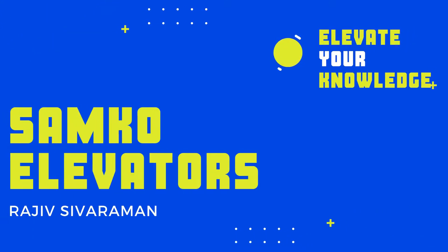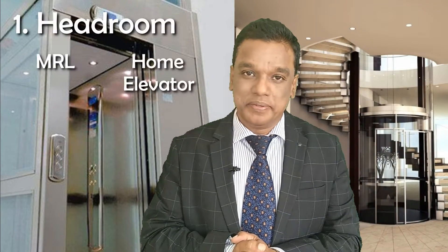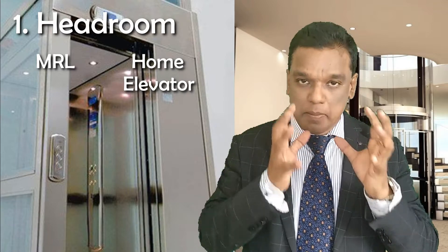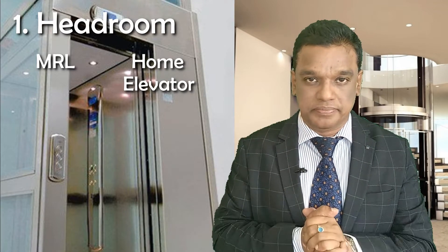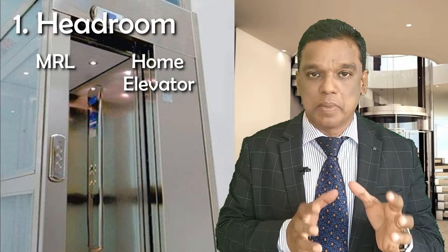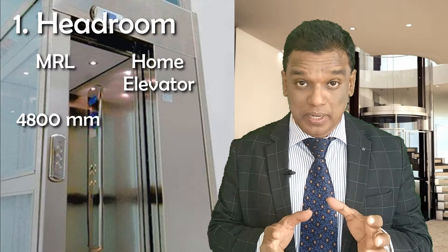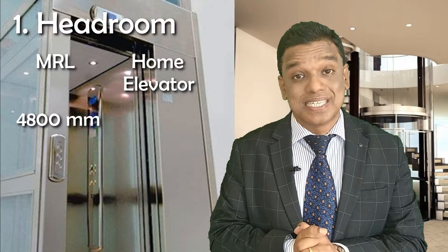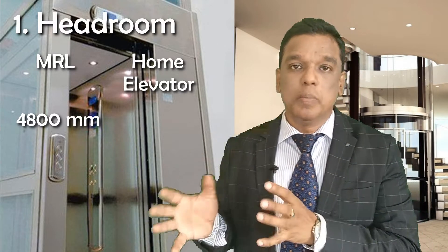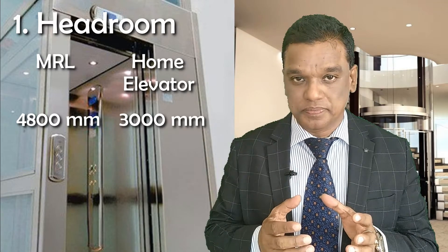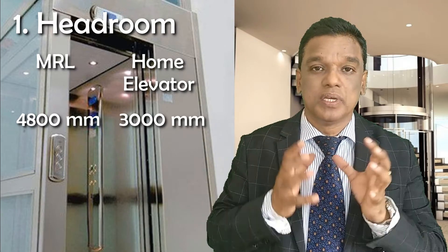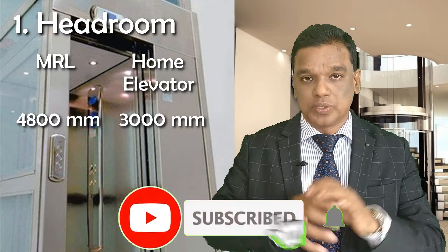Point number one is headroom. In MRL — machine room less elevator — we require a headroom of 4.8 meters, or 4800 mm, which is 16 feet. At the same time, in a home elevator we require a headroom of 3 meters, or 3000 mm. That is the difference in headroom.